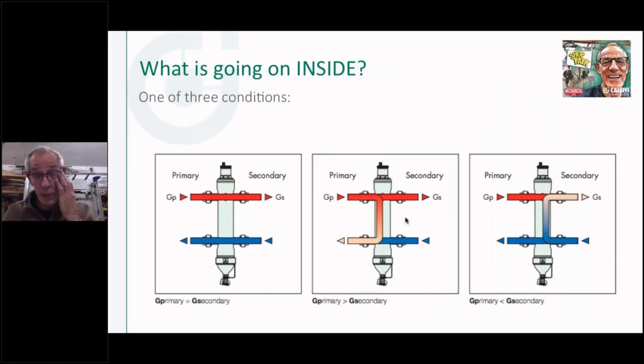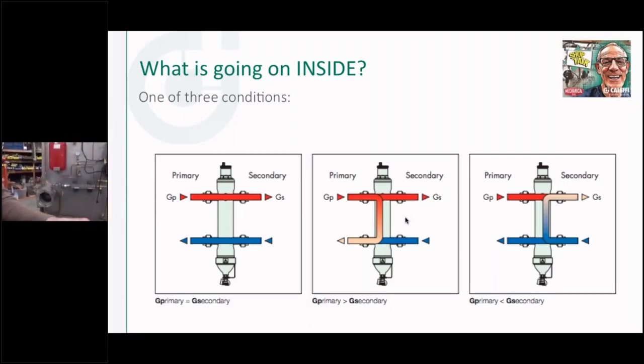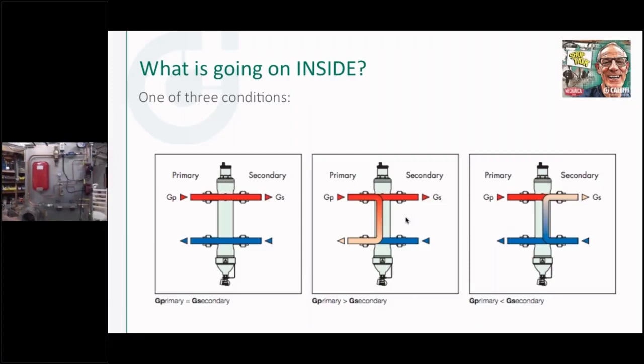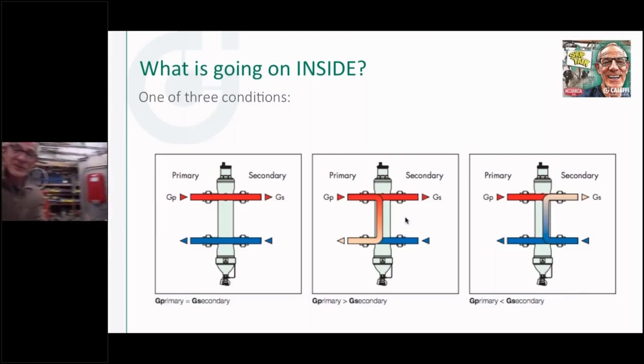I'll show you next week where I could actually pull a negative pressure inside that heat exchanger, that boiler. In fact, I don't know if I can spin it around quickly enough here. I actually put, give me a second here. A little teaser here. I'll turn my screen if you can see that. I've actually put that type of heat exchanger in my little expansion tank display that we're going to show, and there's a compound gauge up there that can go below zero, and I'll show you what happens when things go wrong with that type of setup.